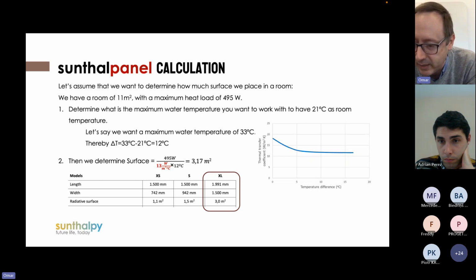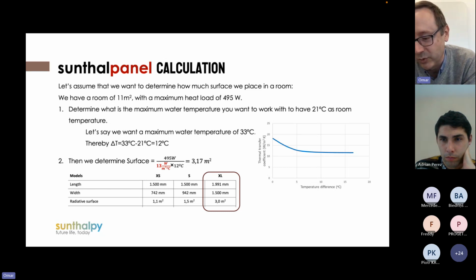For the Sunthalpanel, there's no such limitation — you could introduce water at 60, 70, or even 80 Celsius, and it will withstand those temperatures without trouble. But that's not the idea; you could use it as a fancy radiator, but that's not the objective. We want the heat pump to perform at its best, so the dimensioning should make it appropriate to work at low temperature conditions.